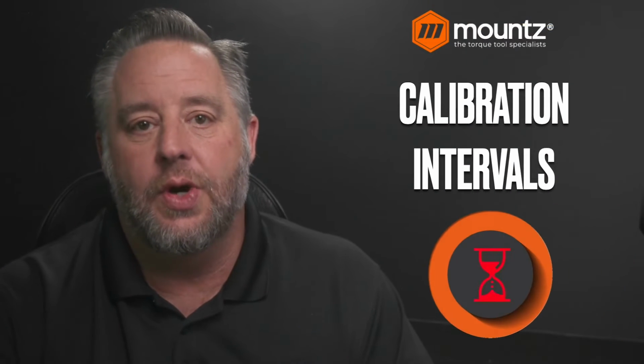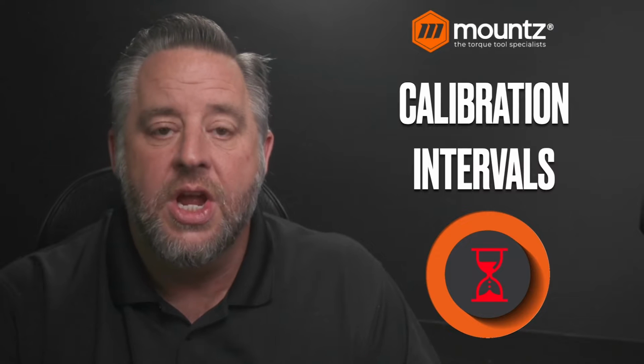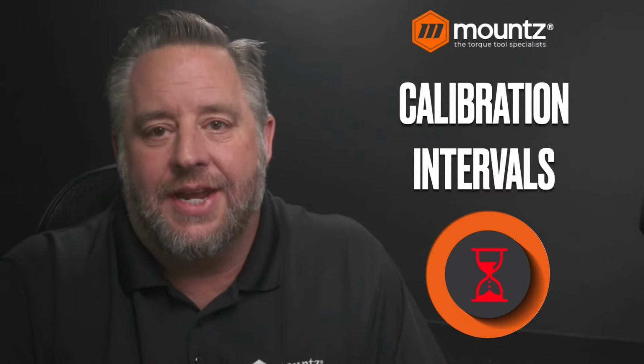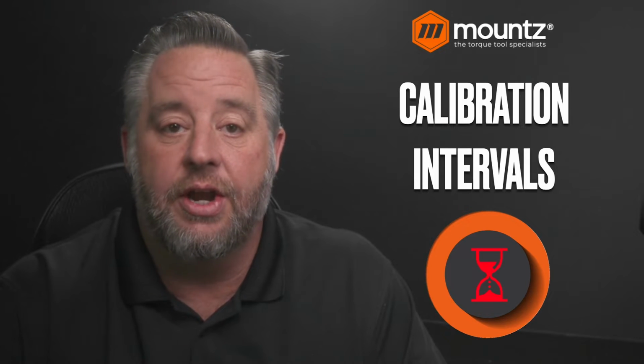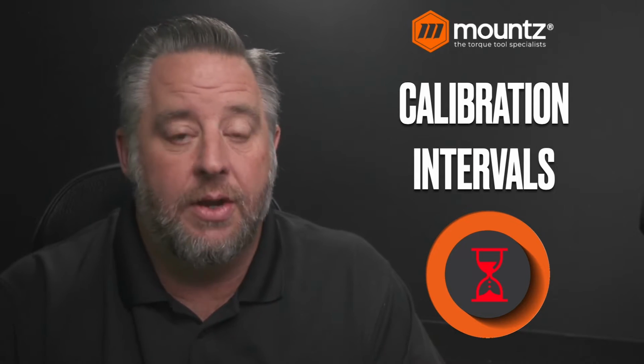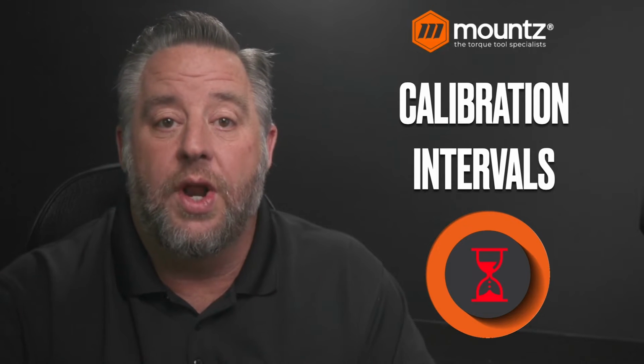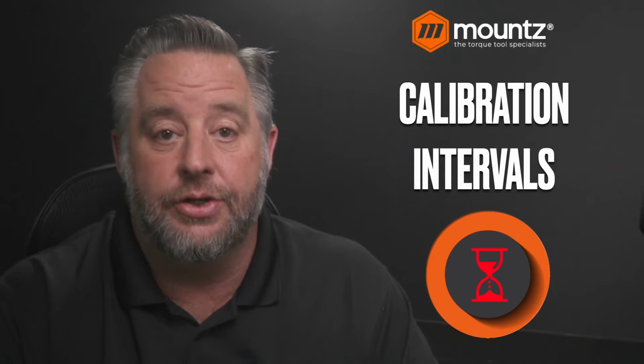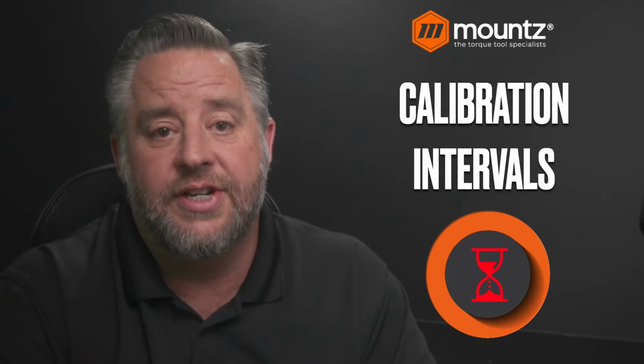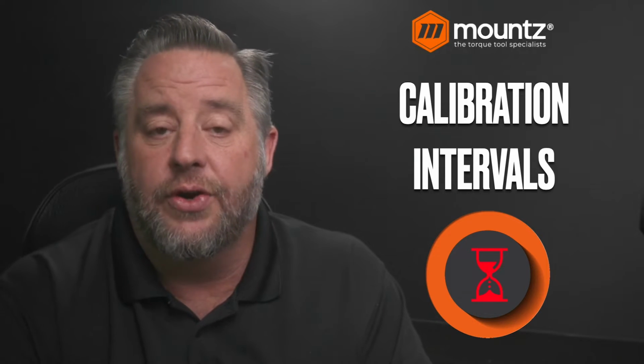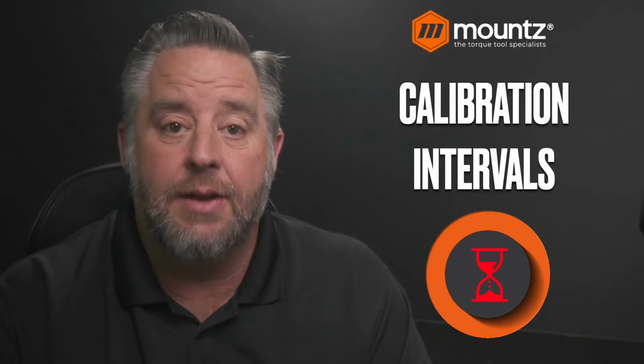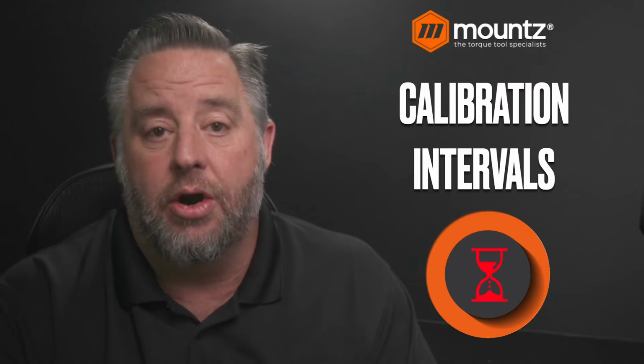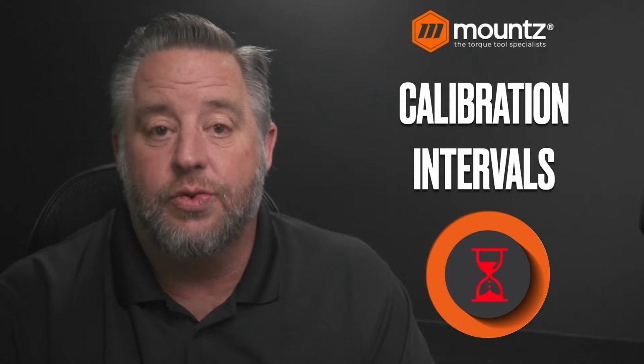And so that will bring us to, when we do our calibrations for our sensors or analyzers, what calibration intervals do we need? At Mountz, we recommend 6 months for you to begin at that rate. We do have customers that would like to see their intervals set to 12 months. And then we have some that will extend that out based off of whatever performance they might see from their analyzers. So if you start at 6 months and you see after the first initial calibration that the readings are well within specification, you can extend that to 12 months.